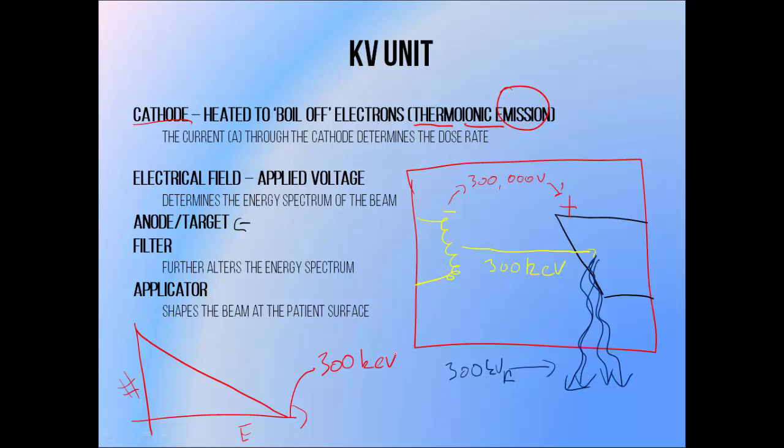The number of photons coming out of the tube will determine the dose rate. We can control this by controlling the current through the cathode, which — if you've ever seen diagnostic x-ray equipment in use — this is the milliamp, or mA setting. Increasing the current means more electrons passing through the cathode, which means more of them are being shaken out into the tube, accelerated towards the target, undergoing the bremsstrahlung interaction and producing photons, which means more photons and therefore more dose.